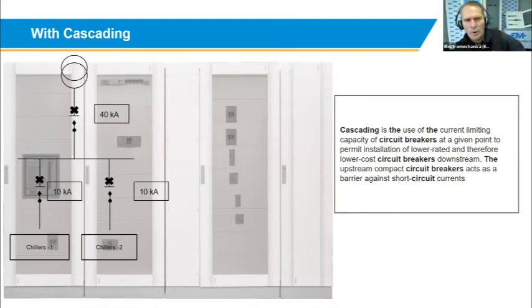So why would you use cascading in the first place? In this scenario, you've got your Quadro Plus distribution board at the back. This board is rated at 40 kA short circuit capability, so your main incomer must be 40 kA. Now you go downstream from this, and you want to protect the light circuit, a 10 amp light circuit, or a 20 amp plug circuit. To put in a 40 kA moulded case circuit breaker here to give you a fully rated board is fairly expensive. This board will also then go much bigger because it takes a lot of space up, and it becomes just a big, massive problem.